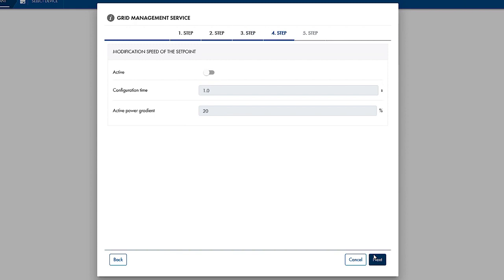Using the rate of set point change, you can define a ramp for how quickly the active power is to change for each second value that has been set. For some grid operators, it is important for grid stability reasons for the active power feed-in not to change suddenly, but instead to change via a ramp. This is the case for dynamic limited active power reduction, for example 70%.